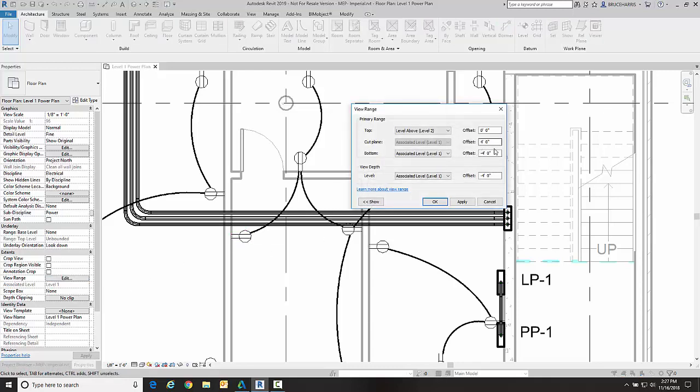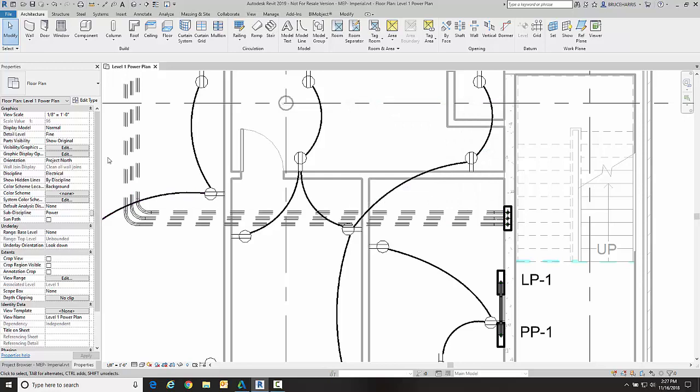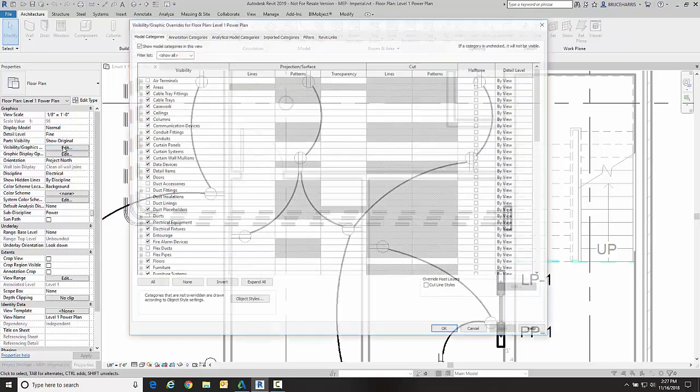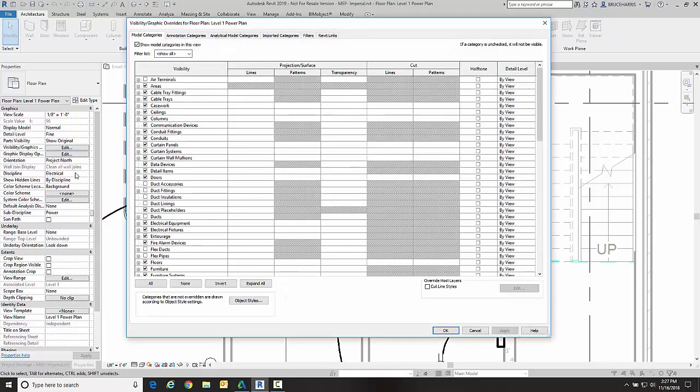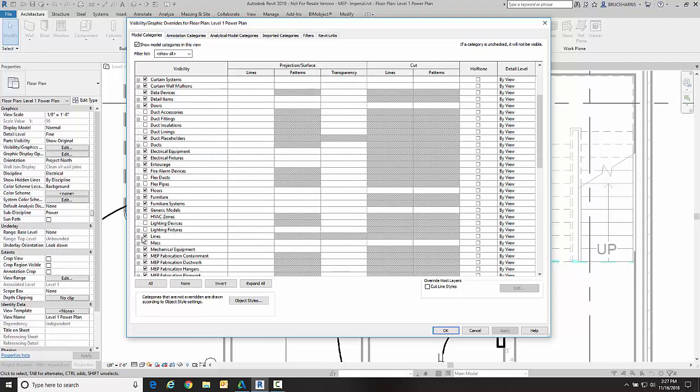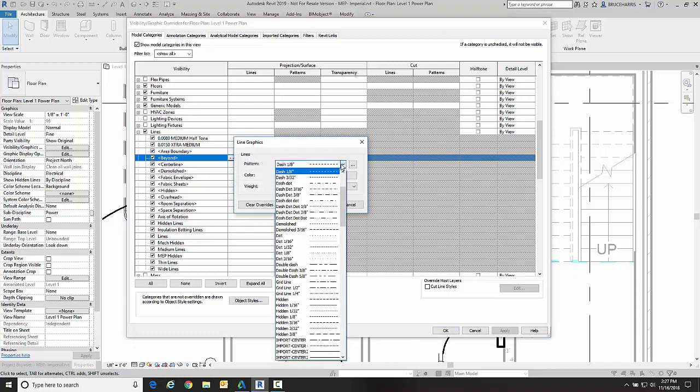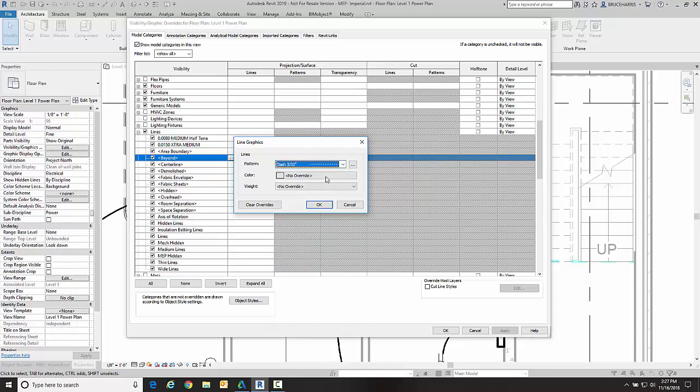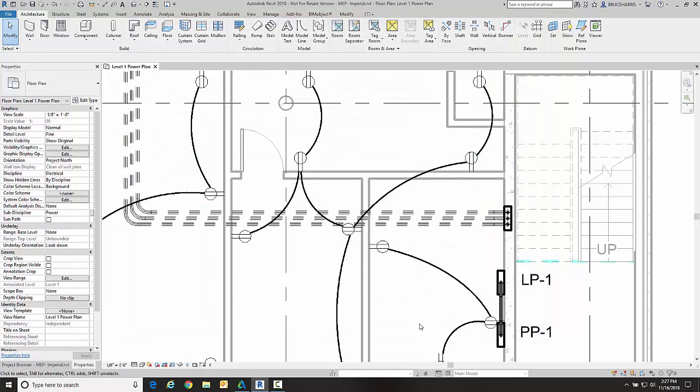Let me go change my view depth back to zero at the bottom. Remember it was in visibility graphics, Lines, and Beyond. I'm going to go ahead and change it and make it even a little bit finer than that, so let's make it three thirty-seconds and go okay and okay. Now my line work below the slab, my conduit in this case, is displayed differently than my conduit above ground.